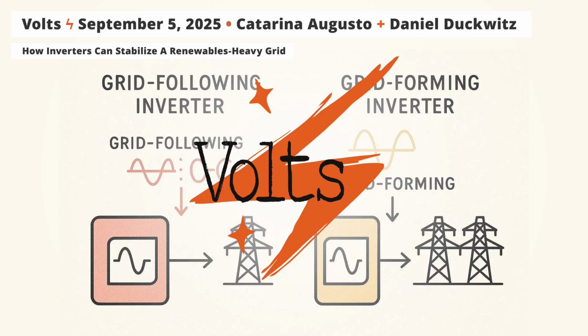At the moment we are dealing with a specific transition where rotating machines are being removed. But also in the past there have been events where low inertia power systems were operated - systems that focus on hydro energy, because the turbines in hydro have a higher power density, since water has a higher power density compared to steam. That means the turbine has less mass, less inertia. Power systems that have focused on hydro, like parts of Canada, maybe parts of the US, or Norway, always had their engineering work to do regarding frequency control.